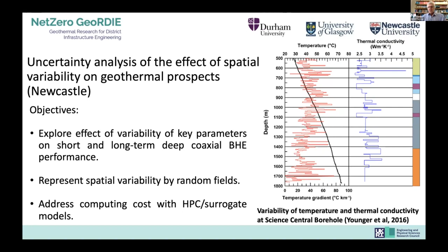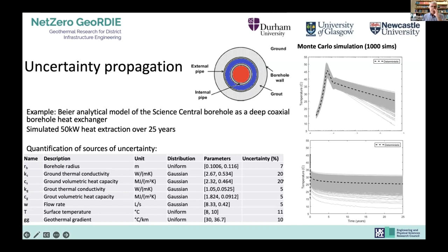These factors have to be taken into account in the models we've just been looking at. Uncertainty analysis tells us which parameters to focus on, since particular parameters have the greatest influence. Using the same model and the same heat load as Glasgow used in their finite element models, 50 kilowatts over 25 years, we did a Monte Carlo simulation over 1,000 runs, and found that ground thermal conductivity and heat capacity are rather important.